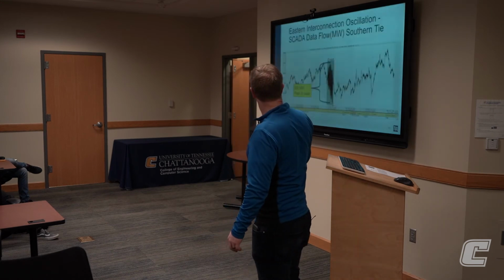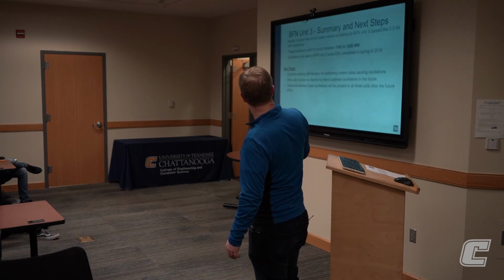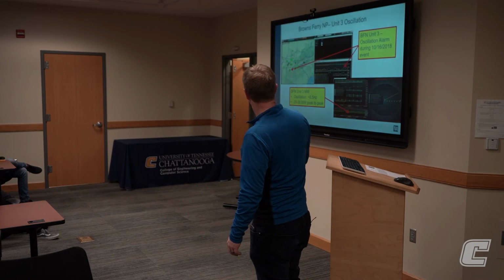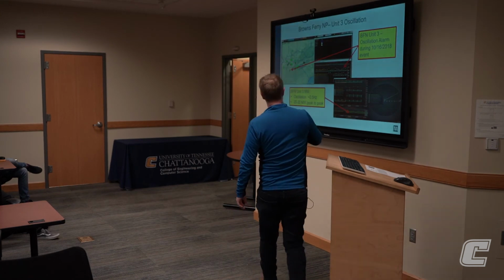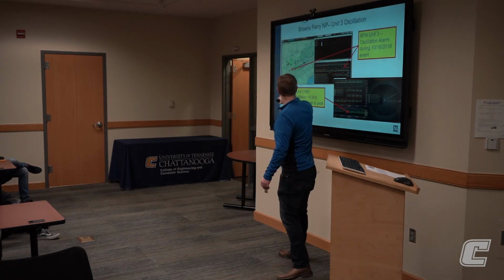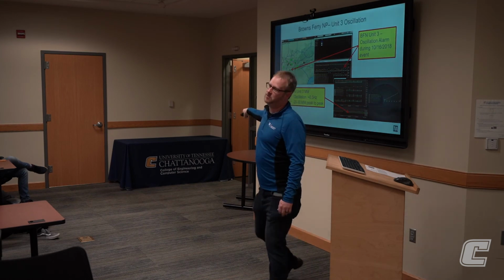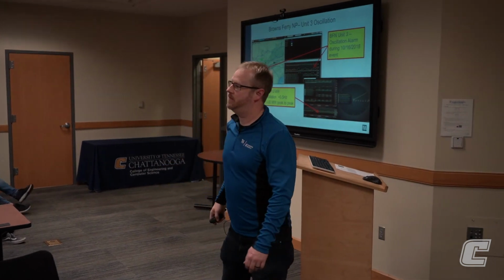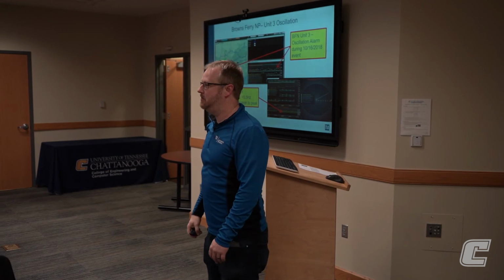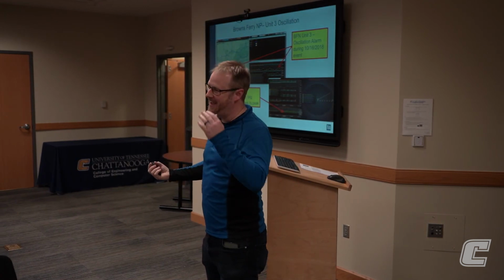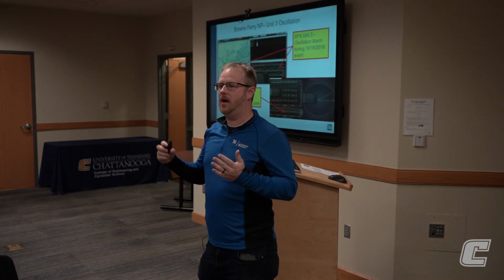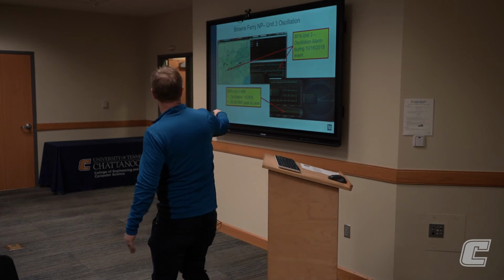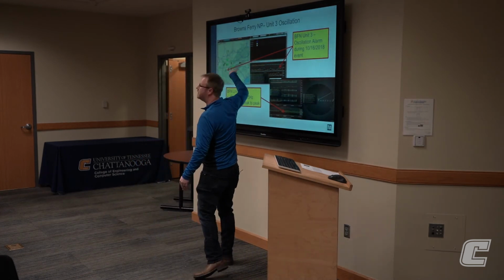When we were looking at this, Brown's Ferry, this is bad, but it stayed local. It was 0.5 hertz. We don't have a natural mode identified around 0.5 hertz, so the only thing that's going to get damaged here is really just our unit, which is bad, but hopefully we're not impacting others, like Southern and Duke that tie to us.